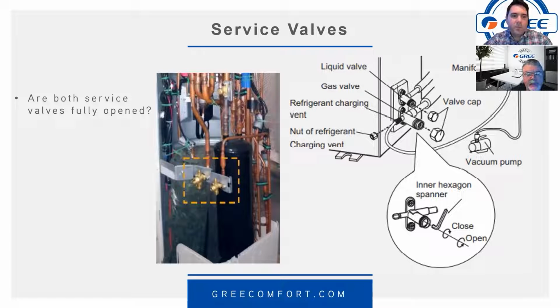And the other thing is you don't have to wrench on these things when you're backing them out. Back them out gently. You don't have to put a cheater pipe on there to get them open fully, but back them out all the way and then just give them a little nudge back in, and you should be good to go. We've actually, Richard in tech, wrenched on those things just to see how robust they were, what it would take, and he actually cranked one of the valves all the way out. So it's called a non-backseating valve is the term that Richard schooled me on the difference between the two. And some manufacturers will have a note that says turn a quarter turn back in once you've backed it out, just to make sure that it's not going to leak.